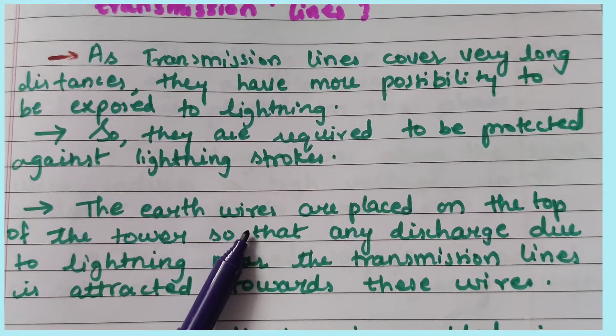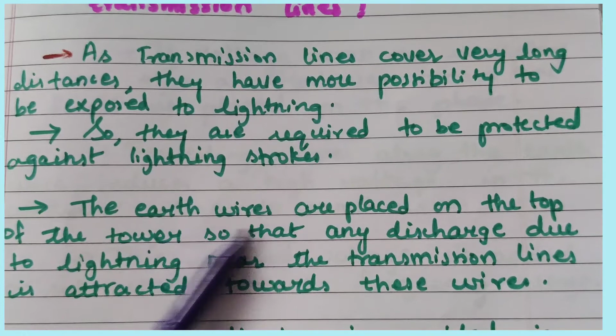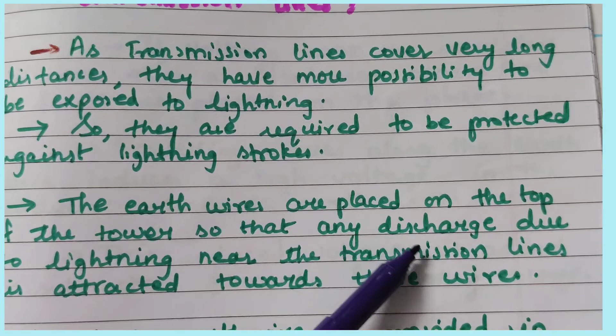So they are required to be protected against these lightning strokes. This is done by providing them with earth wire, placed on top of the tower. Whenever lightning happens, these earth wires discharge that extra overvoltage into the earth. Any discharge due to lightning near the transmission lines is attracted towards these wires.